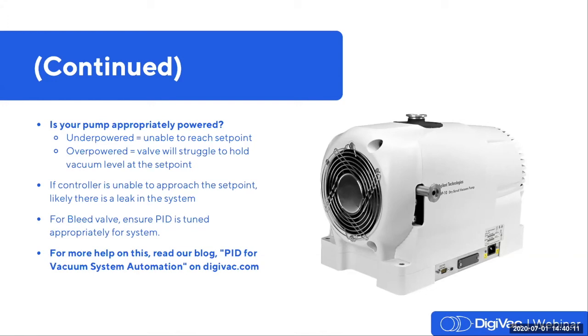An underpowered vacuum pump will not be able to achieve the set point at all, and an overpowered vacuum pump will struggle to hold the vacuum level at that set point. Also, if a controller is unable to approach the set point, there may be a leak in the system. Make sure to check all of your threaded and flanged connections.